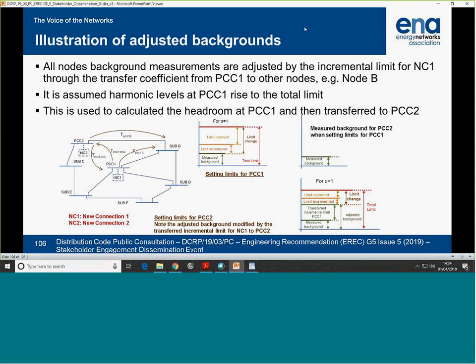In theory, you can still shift the load, so it can all go from one side to all on the other. You've got two transformers at 50%, and you'd make it one transformer at 100% if that occurred, but the load won't change, will it? No, the harmonics are the same, just the way you're feeding it. But the harmonics would be less. You'd split the harmonics across both in normal operation, but if you lose one, all the harmonics would go one way or the other.